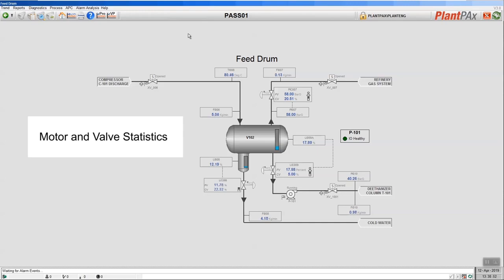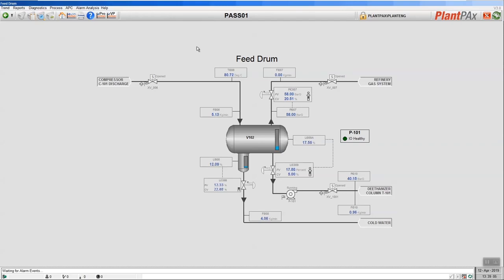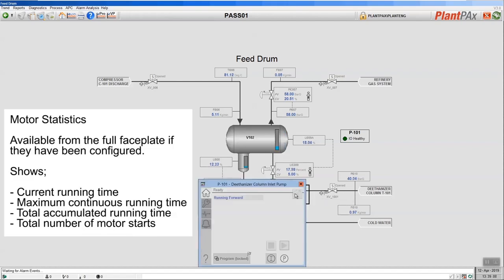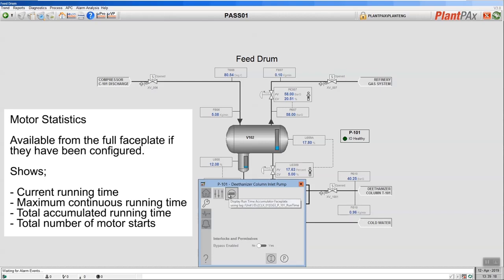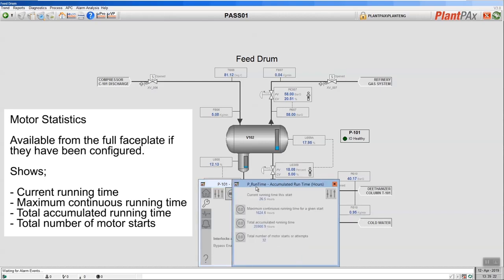In this video we're going to look at the statistics objects that are available for both motor objects and two-position and three-position valve objects in the library of process objects. Let's first look at the motor statistics object. I'm going to open up the motor faceplate and go into the maintenance section so that I can access the statistics for this motor. Here we have the statistics for the motor — you can see the current running hours, the maximum continuous running time for any given run, the total accumulated running time, and the number of start attempts for that motor.